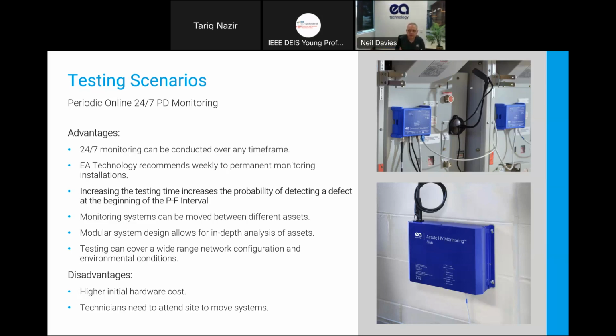High voltage is the primary stress, and it's not hugely affected by load. It's more by the voltage, but at certain times where the load goes high, you might get some expansion and contraction of certain components. So we've seen load-related defects. So testing over maybe a week with different loading conditions and different environmental conditions can give you information that you're not going to get from a spot check. Of course, the disadvantage of using this system is higher hardware cost, and then you need the technicians to move the systems around the site. So it's the time element again.